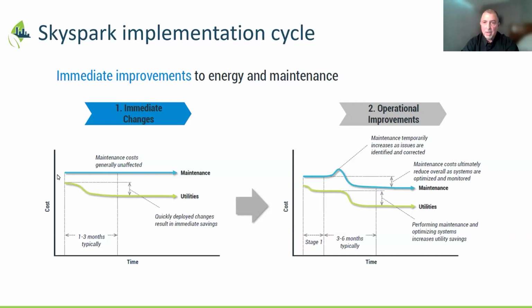That's not really a fault, the equipment is operating correctly, but there's an issue. First stage, as operators and partners look at the fault detection project, you get that information lined up, then start realizing you have some equipment issues. For example, dampers stuck open, bringing in air and reheating or dehumidifying it when we shouldn't be. That requires a labor dollar value, a budget for labor to go fix that damper.